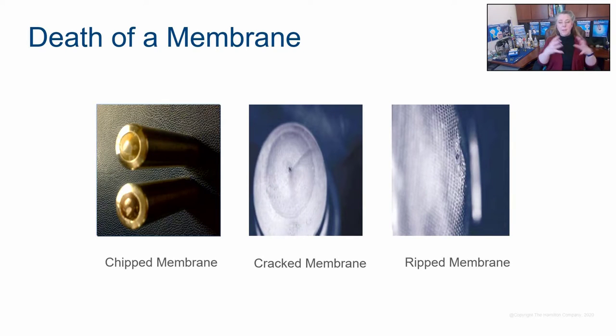Okay, membranes over time also get old and they need to be disposed of. There's a couple things that we need to take into account with that. So the first one that you see on the left is the chipped membrane. Over time, in process, in function, in usage, these will get chipped, and that's just age. You generally only get a couple months of lifetime for the cap of these probes. Cracked membranes happen when you place these probes down on a surface. That mere act of putting them on the surface can cause tiny microcracks. Why is that important? Well, that ties into the third one.